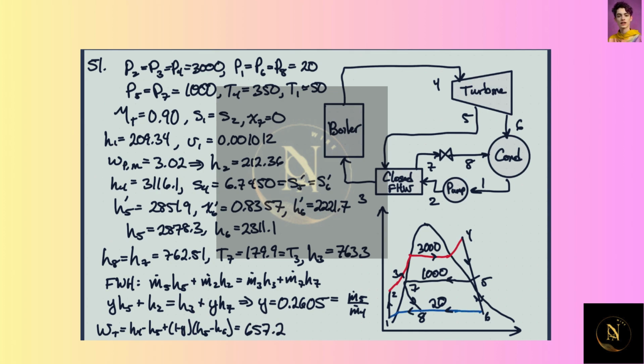Is it H3 that changed? No, it's H2 that changed. So again, by having a lower enthalpy here, we have more bleed off here, which means that we have less power out of the turbine. All right, yep, that makes sense. It's not very intuitive though that subcooling would affect things very much, but it does quite a bit actually, by 10 degrees C. So we don't want to do that if we can avoid it.